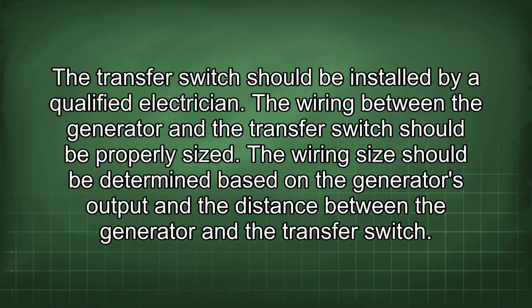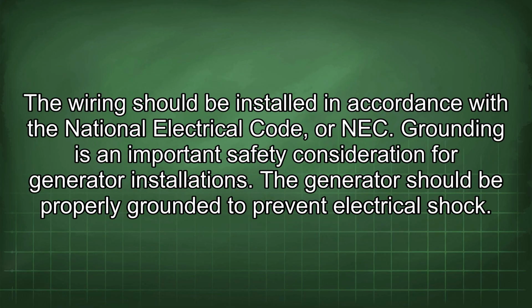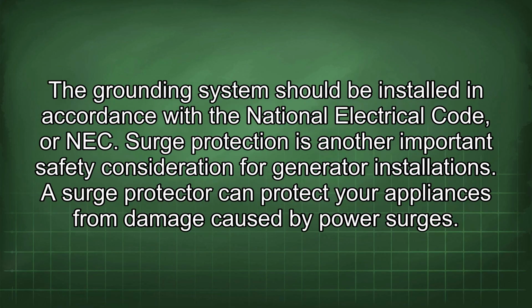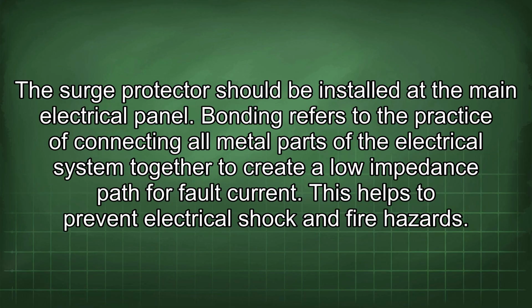The wiring between the generator and the transfer switch should be properly sized. The wiring size should be determined based on the generator's output and the distance between the generator and the transfer switch. The wiring should be installed in accordance with the National Electrical Code, or NEC. Grounding is an important safety consideration for generator installations. The generator should be properly grounded to prevent electrical shock. The grounding system should be installed in accordance with the National Electrical Code, or NEC. Surge protection is another important safety consideration for generator installations. A surge protector can protect your appliances from damage caused by power surges. The surge protector should be installed at the main electrical panel.